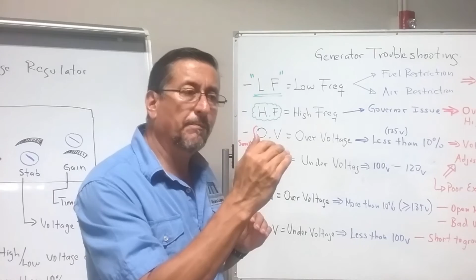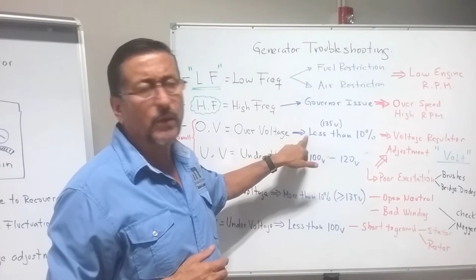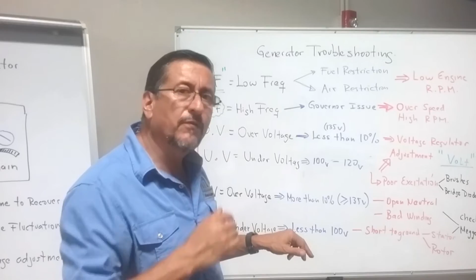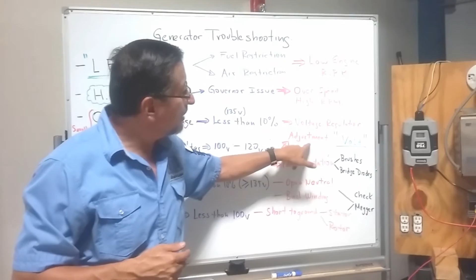If the overvoltage or undervoltage is only 10% higher or 10% lower, in both cases you can calibrate at the voltage regulator. Right now I am going to explain the procedure, only if the deviation is no more than 10%. For example, if the output voltage is not 120, it is 135, that excess of voltage can be reduced if you calibrate the voltage pot at the voltage regulator.